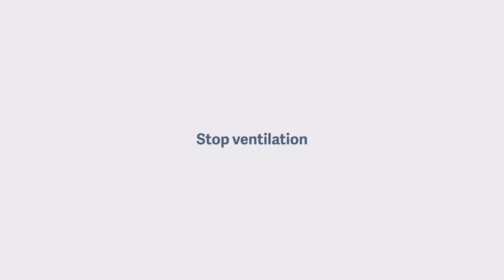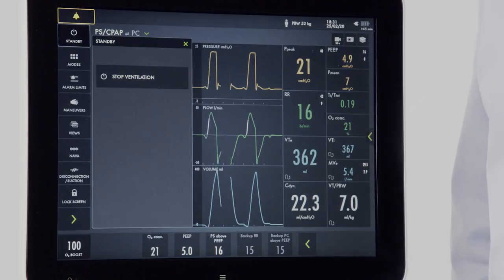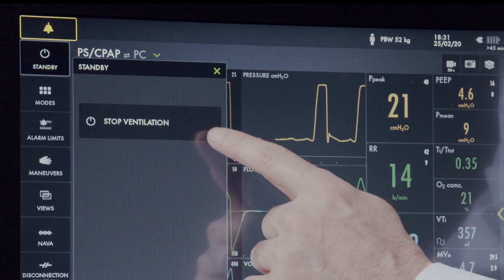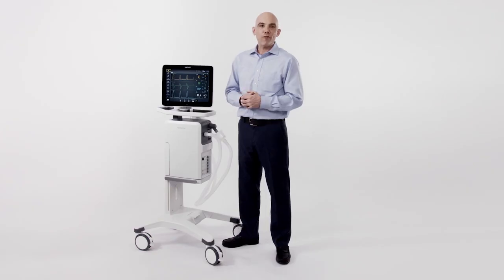To stop ventilation and put the machine in standby, press the standby key. That button alone will not discontinue ventilation — there is a second safety step required to stop the ventilator. From here, I have a stop ventilation button. Pressing and holding this button for two seconds will place the device in standby. This concludes our orientation to the Servo-U ventilator. Thank you for joining me today. Please be on the lookout for new videos and e-learnings from Getinge.